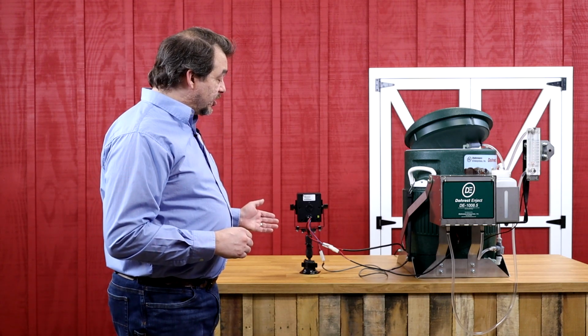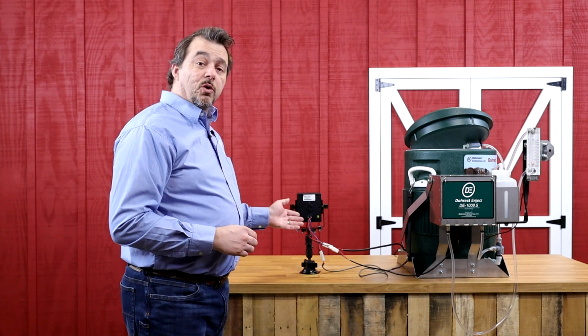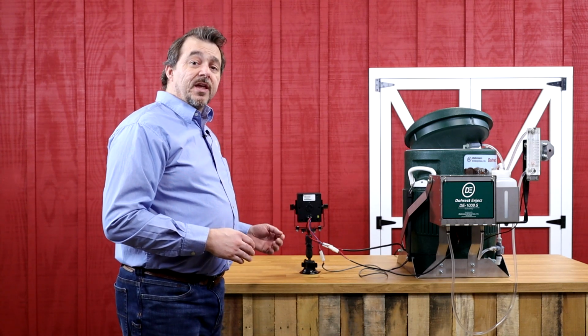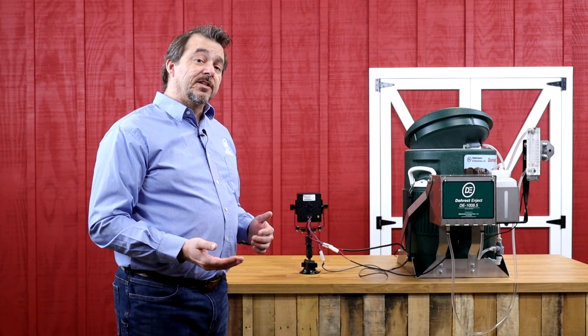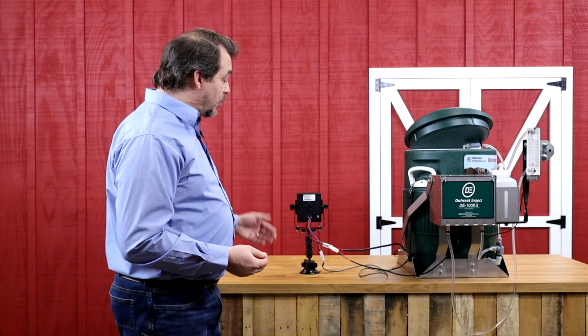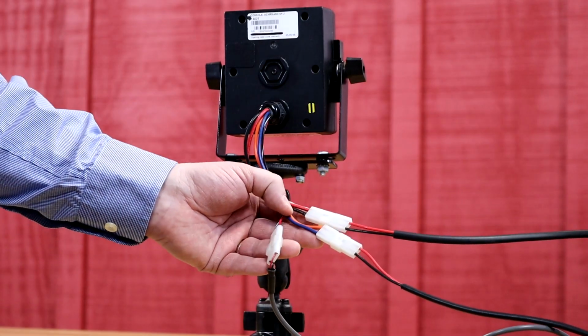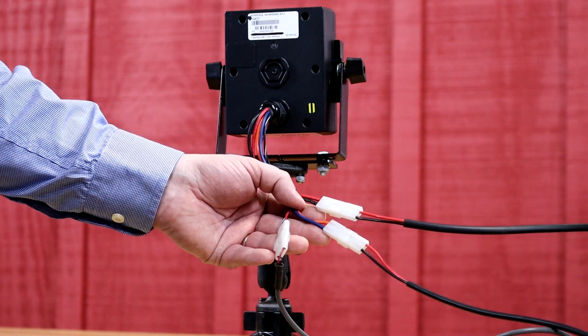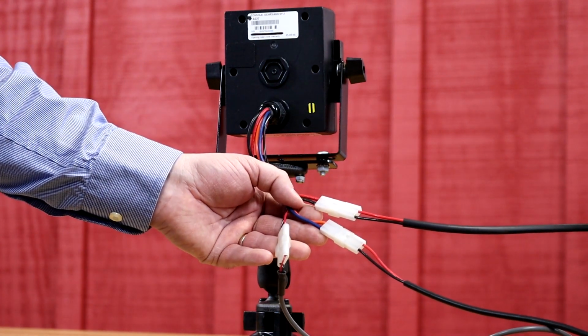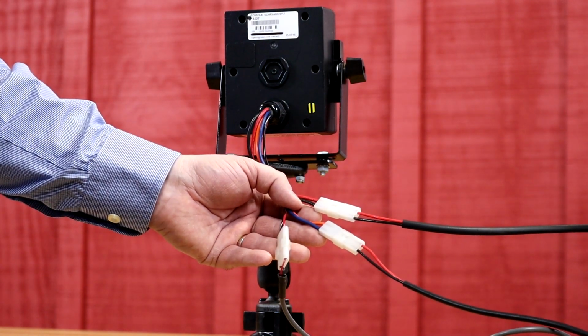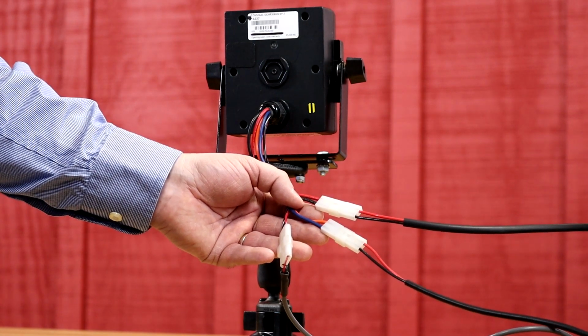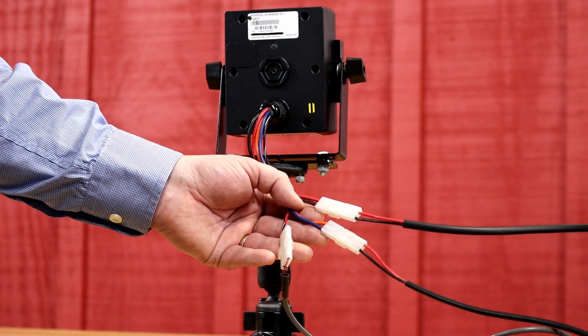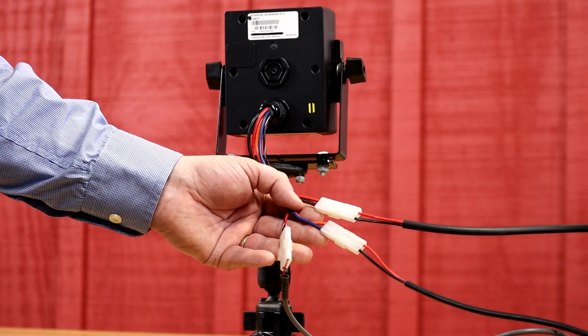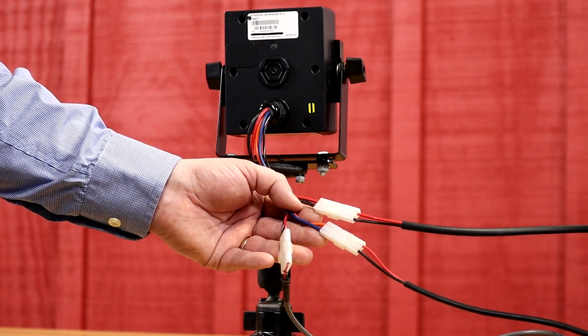But first we have to determine if the problem lies within the controller or the power supply. And to do that, we're going to bypass the control. Now, depending upon which model you have, you're either going to have 2 or 3 different connections on the back of the controller. The older SP2 control will only have 2 connections, whereas the SP2L will have 3. We're only going to worry about 2 of those connections.